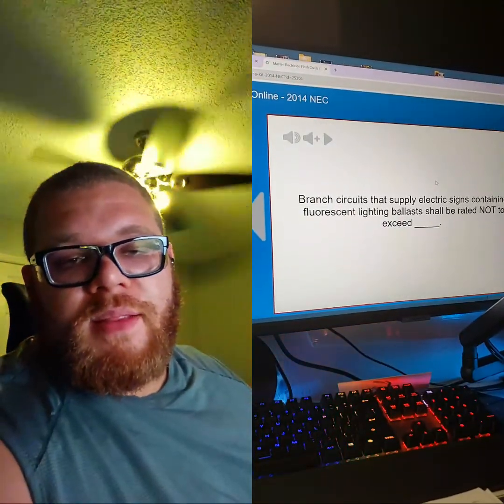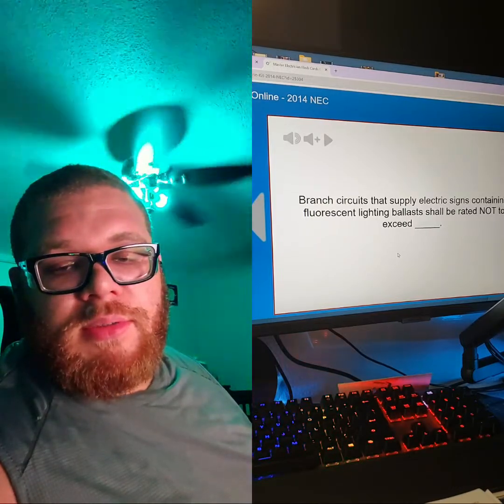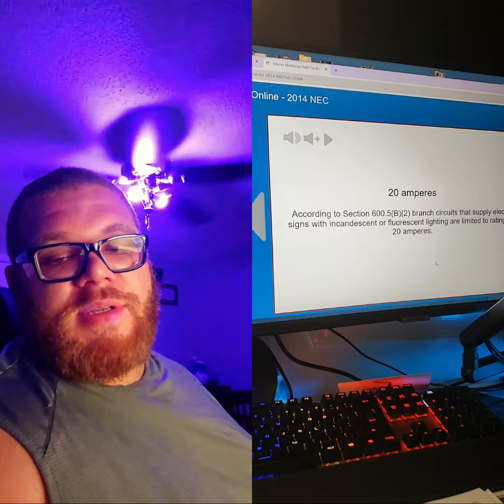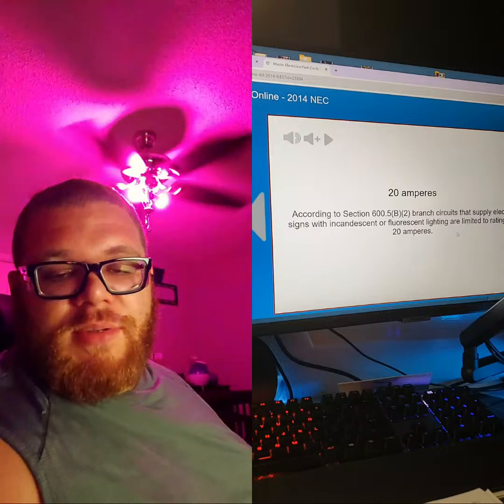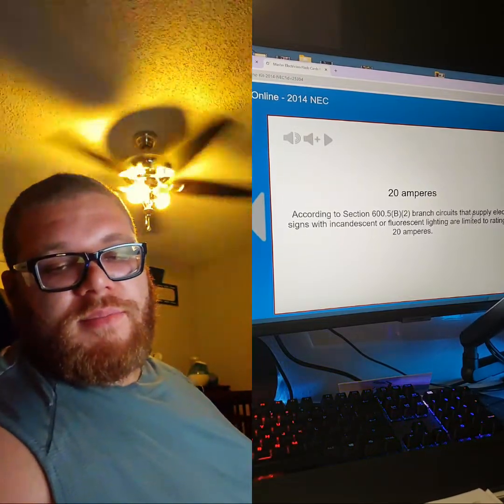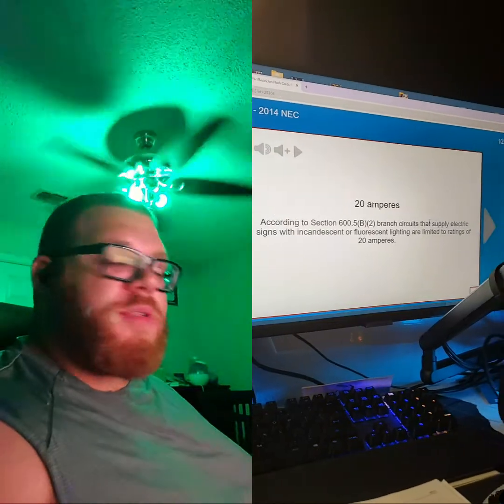When you see that it says continuous duty, that multiplying factor is 1.25, just so you know. Right. So your sign is really going to be 16 amps, or not to exceed 16 amps, and your circuit not to exceed 20. Right. You're going to look at 80% of your 20 amps.